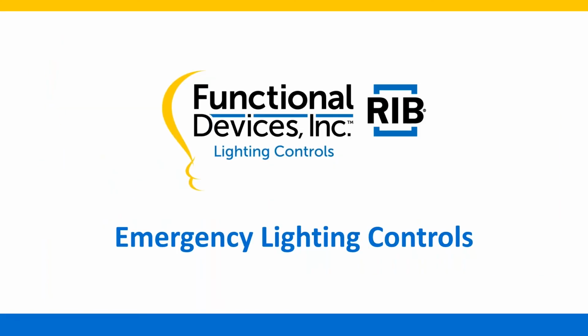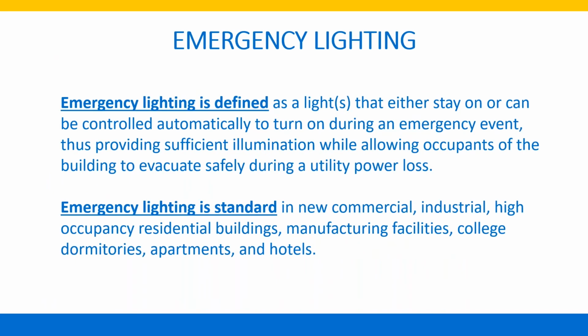In this section, I will be going over our emergency lighting and its code requirements. Emergency lighting is defined as light or lights that either stay on or can be controlled automatically to turn on during an emergency event, providing sufficient illumination while allowing occupants of the building to evacuate safely during a utility power loss. Emergency lighting is the most important section when it comes to a lighting control layout.